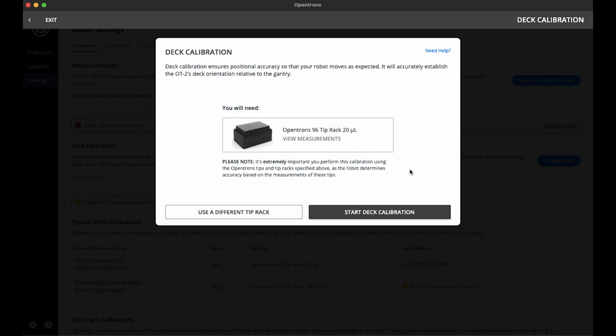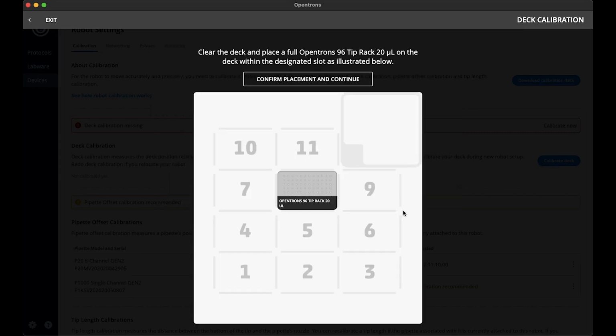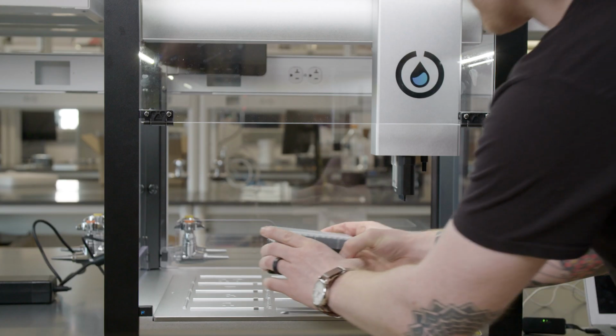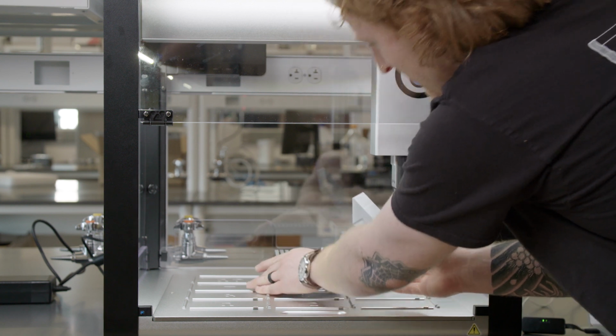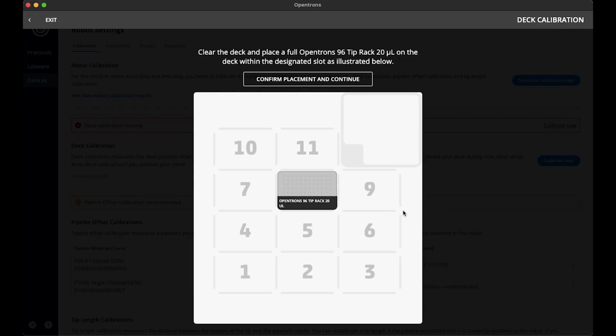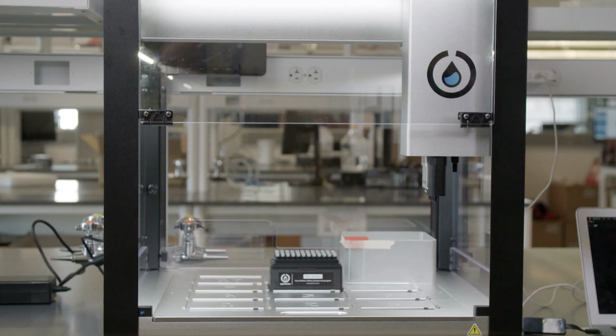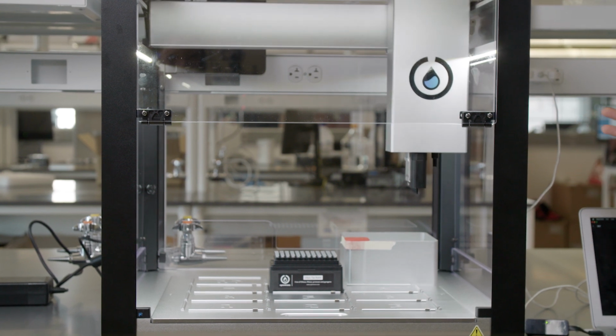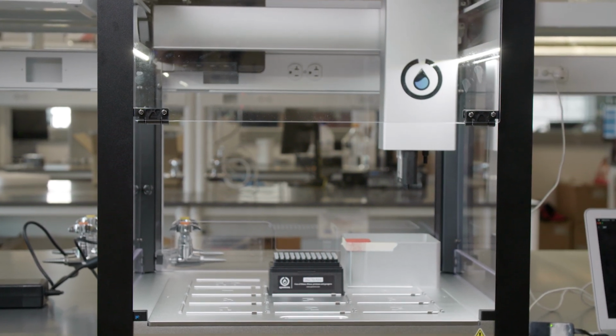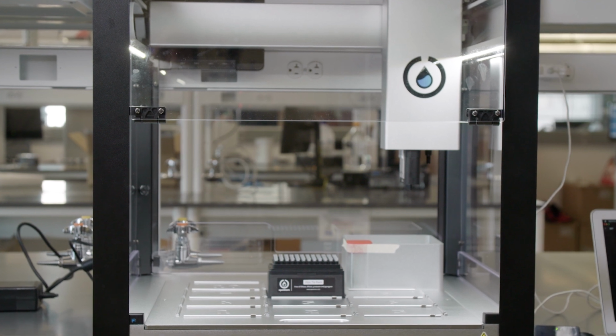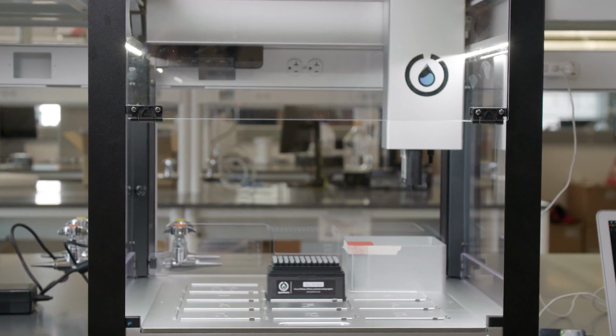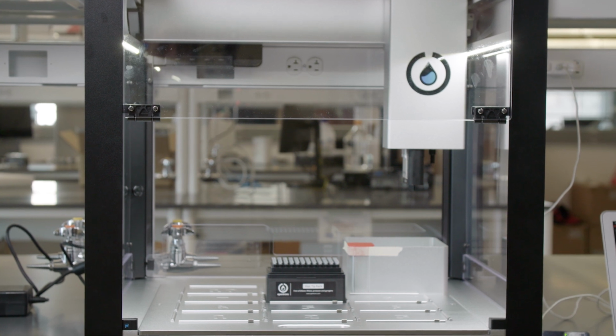The app will tell me what I need for the deck calibration. I will need the Opentrons tip racks, so we'll start deck calibration. I then need to place the tip racks in the correct slot, which is slot 8 on the deck, making sure to take the top off. Next, I'll confirm placement and continue. The OT-2 will now home, and then it will position itself so the backmost nozzle is above tip A1.